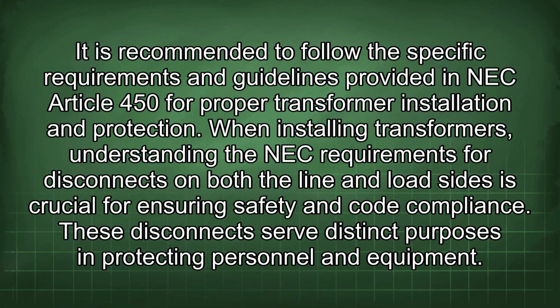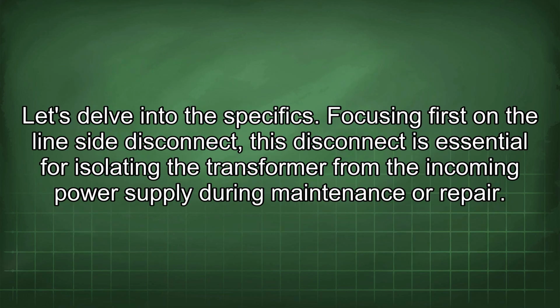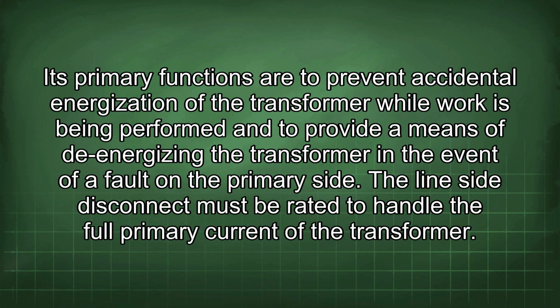These disconnects serve distinct purposes in protecting personnel and equipment. Let's delve into the specifics. Focusing first on the line side disconnect, this disconnect is essential for isolating the transformer from the incoming power supply during maintenance or repair. Its primary functions are to prevent accidental energization of the transformer while work is being performed and to provide a means of de-energizing the transformer in the event of a fault on the primary side.